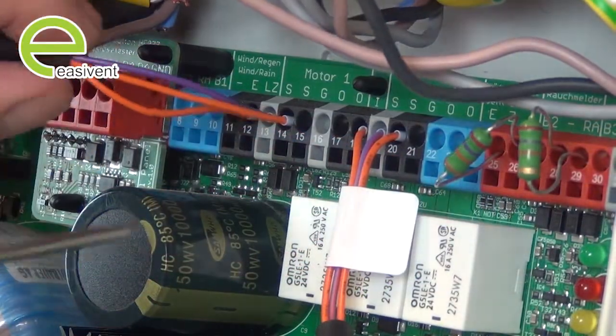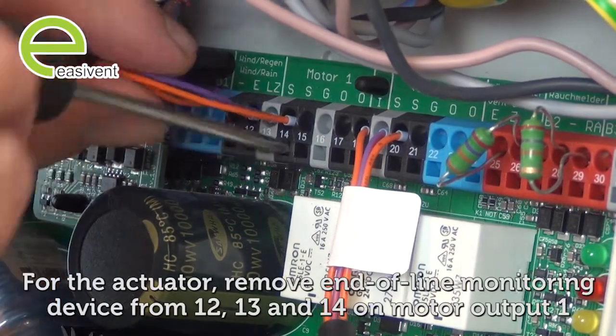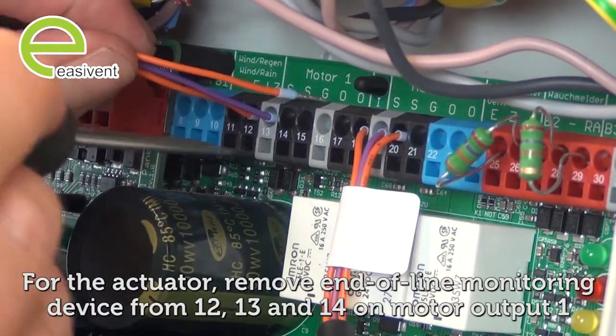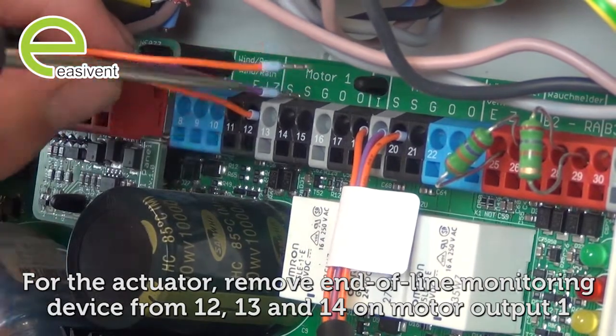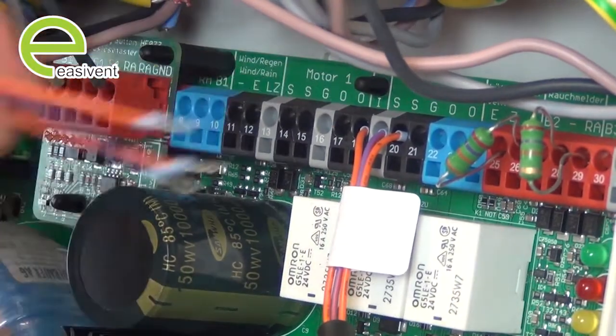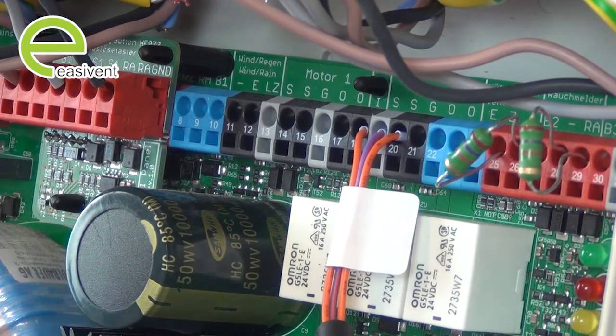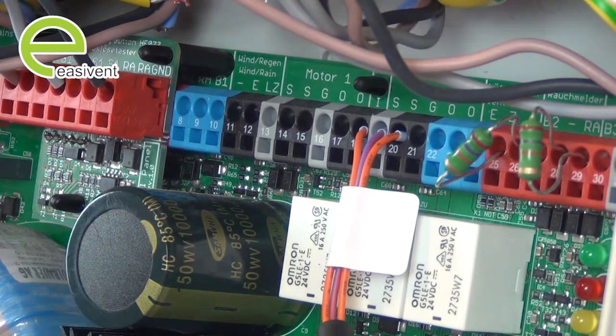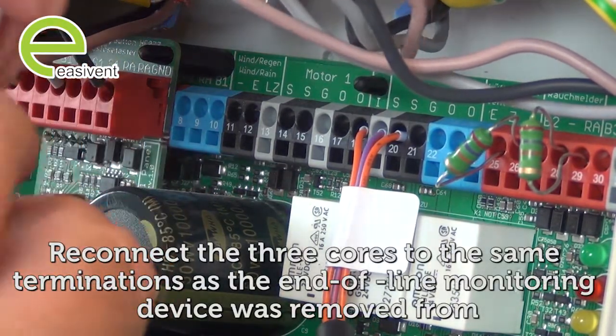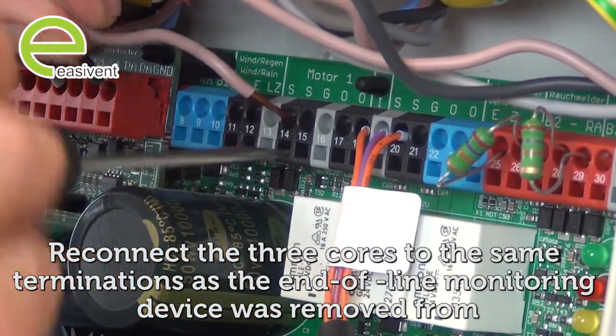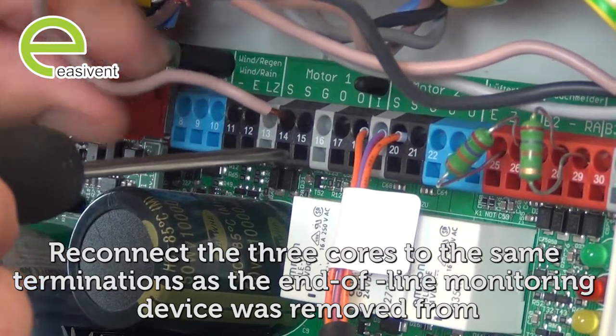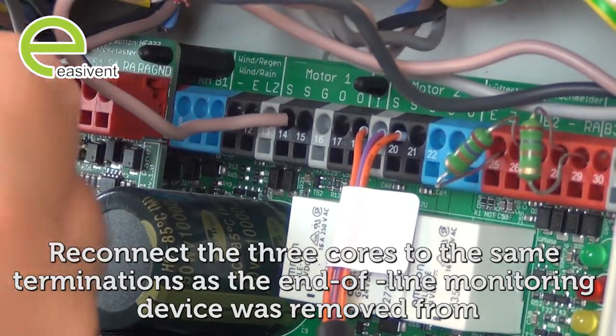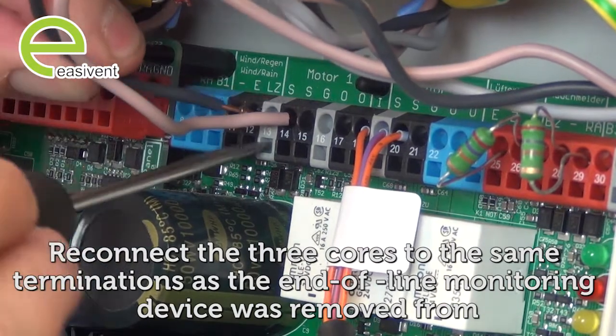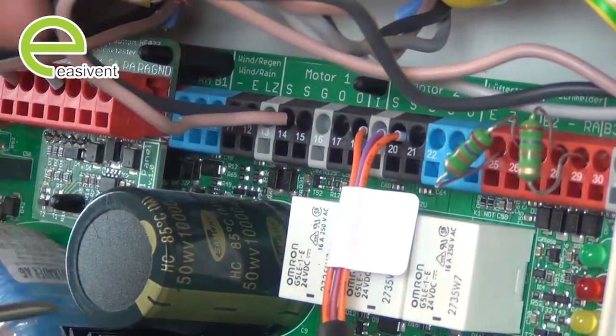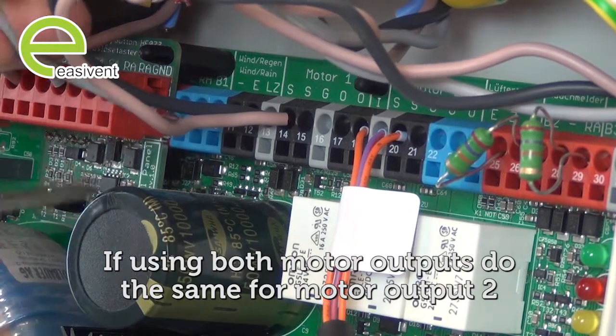For the actuator terminations, simply take out the end of line monitoring device from 12, 13 and 14, on which I put one on the panel. That then goes across the junction box next to the actuator, and reconnect up your three cores which go to the junction box back in, on the same terminations that the end of line device was removed from. Obviously, if you're using both motor outputs, do the same with motor output 2.